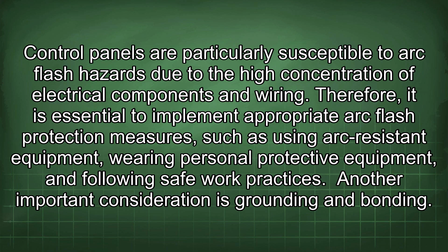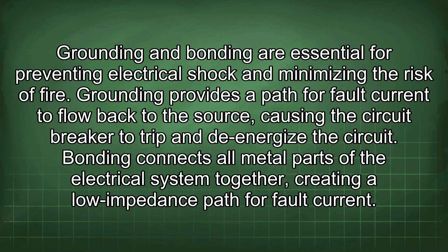Another important consideration is grounding and bonding. Grounding and bonding are essential for preventing electrical shock and minimizing the risk of fire. Grounding provides a path for fault current to flow back to the source, causing the circuit breaker to trip and de-energize the circuit. Bonding connects all metal parts of the electrical system together, creating a low impedance path for fault current. Proper grounding and bonding are critical for ensuring the safety of personnel and equipment.